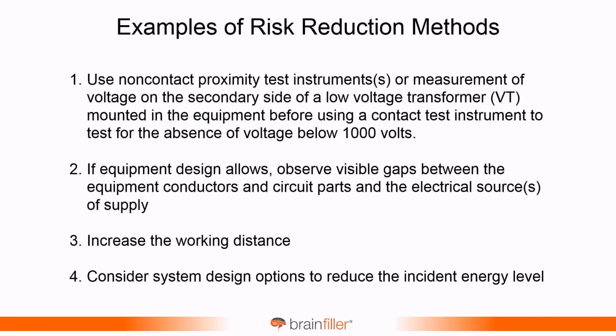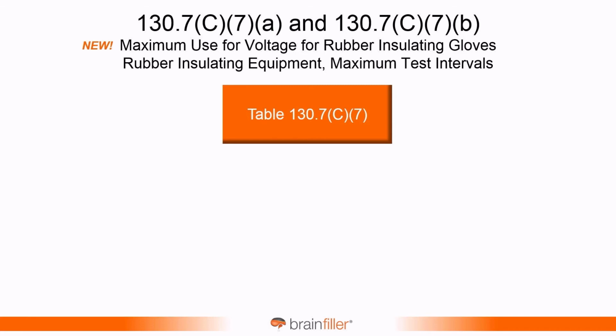Another example of a risk reduction method is to consider different design options, maybe use some type of current limiting device. And remember, I mentioned IEEE 1814. That's going to be coming in, and that's going to give us some options. Another change to the 2021 edition: we have one table that is now part of a pair of tables.